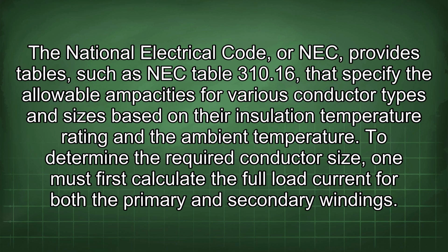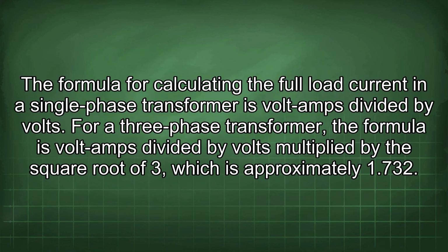To determine the required conductor size, one must first calculate the full load current for both the primary and secondary windings. The formula for calculating the full load current in a single-phase transformer is volt-amps divided by volts. For a three-phase transformer, the formula is volt-amps divided by volts multiplied by the square root of 3, which is approximately 1.732.